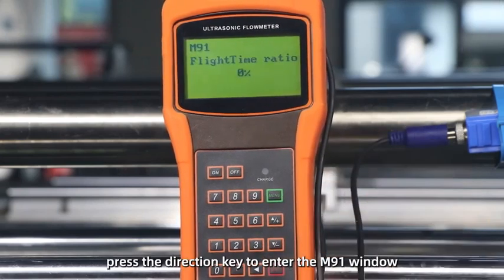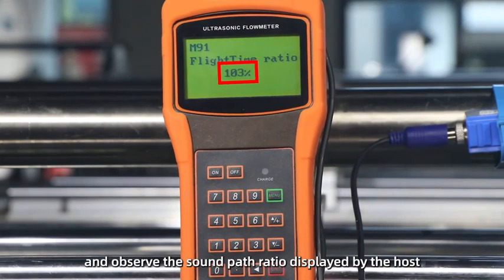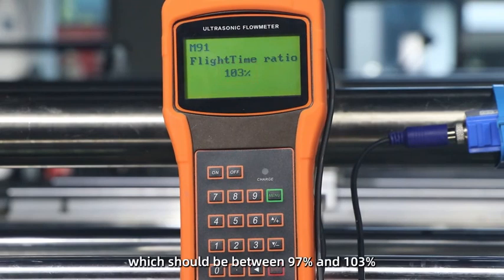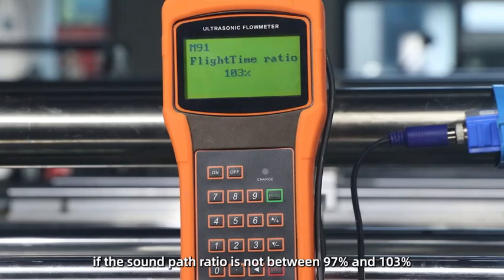Press the direction key to enter the M91 window and observe the sound path ratio displayed by the host, which should be between 97% and 103%. If the sound path ratio is not between 97% and 103%, it means that the set field parameters or the installation distance of the sensor are wrong.